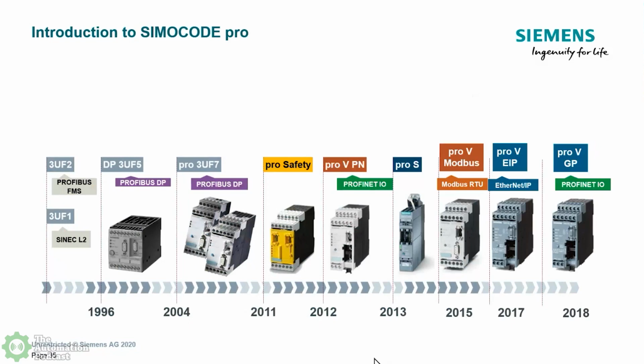If you look closer at the SIMOCODE, you'll see that all the terminal blocks are removable. So once you've installed it and it's been commissioned, you never have to unwire anything. You just unplug the communication protocol, you undo the terminal blocks, you unplug the CT, and then you can replace the SIMOCODE unit and plug in the same terminal blocks, and you never have to unwire anything. And that's 99.9% of the time. There are a few exceptions to that, but 99% of the time, it's just remove terminal blocks, replace the unit, plug it in, and then now the hardware's all ready to roll, and you didn't have to unwire anything or worry about the loop checks again and so forth.